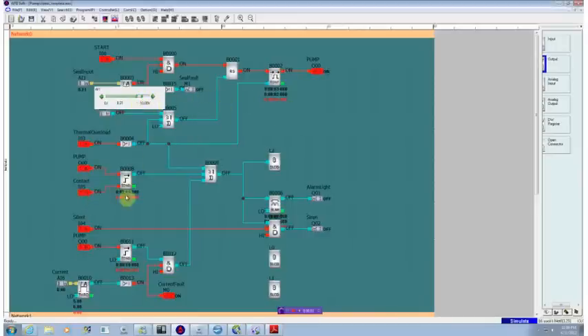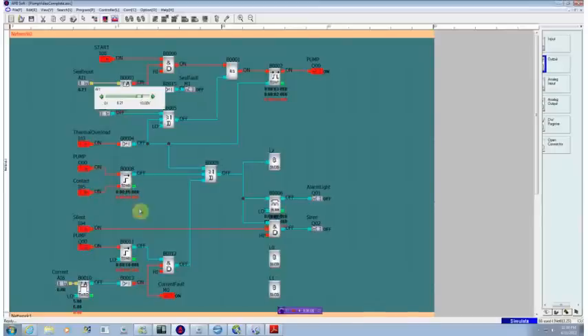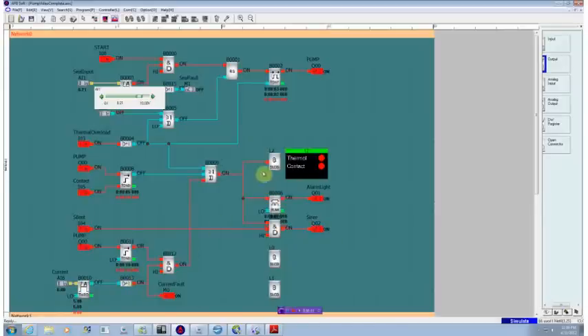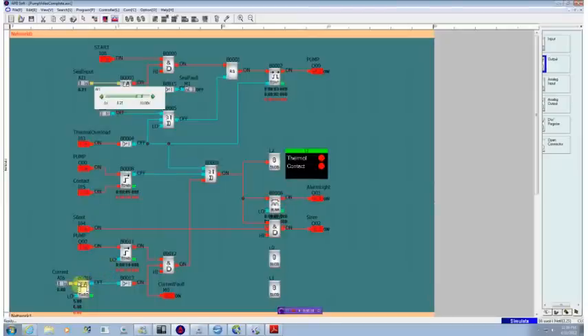Within five seconds, we have to satisfy the current flowing. And this timer is timing out. When it hits ten seconds, we see that we indicate that we have an error condition because we've had no current flowing through the motor.